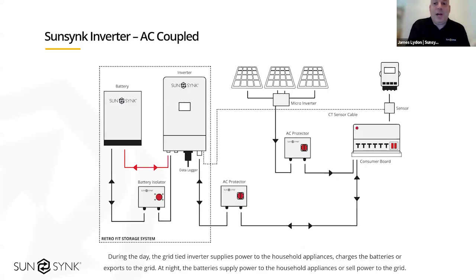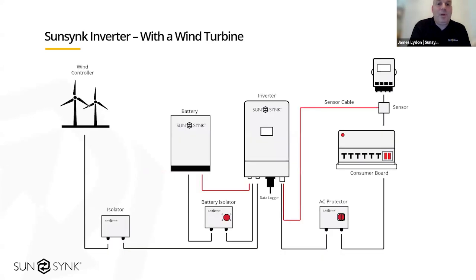Okay, AC coupled. As I mentioned earlier, this is working with a grid-tied system. With the CT placement on our kit, we can monitor what the grid-tied string inverter is doing and what it's exporting to the grid. And we can program, as soon as that string inverter starts exporting, we can divert that power to our connected batteries. Okay, with a wind turbine, again, as mentioned earlier, if the inverter's got 2 inputs on it or 4 inputs, we can split those inputs and have a connected wind turbine. If there's 2 MPPTs, we can have both for solar, both for wind, 1 for solar, 1 for wind.